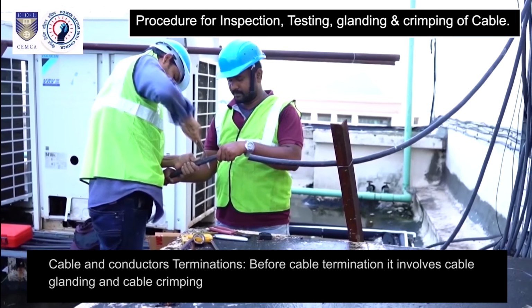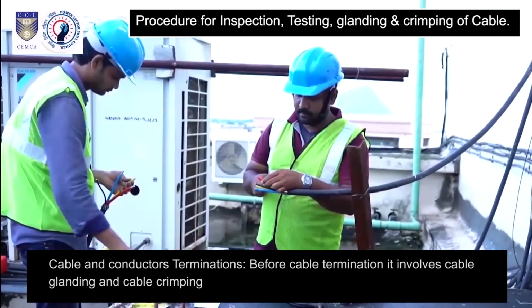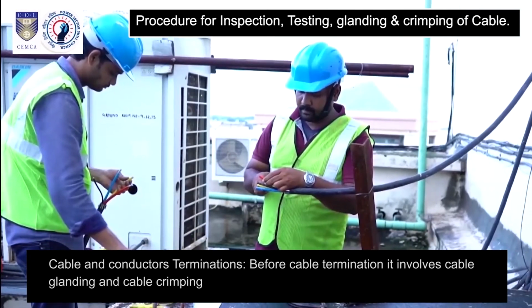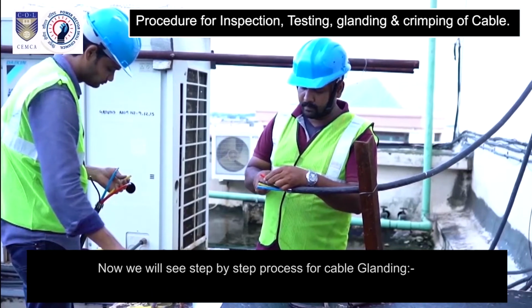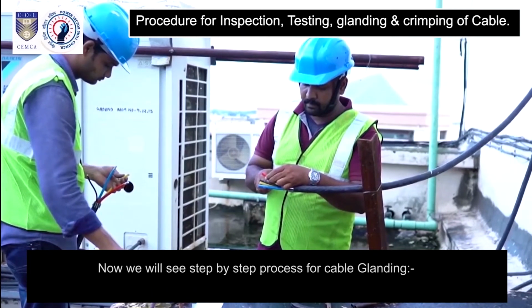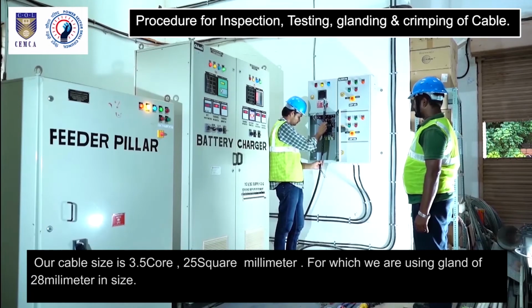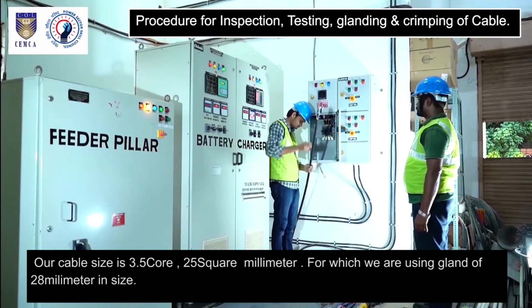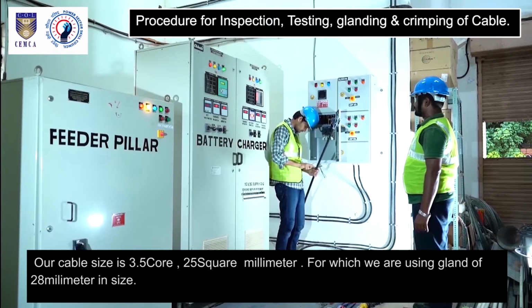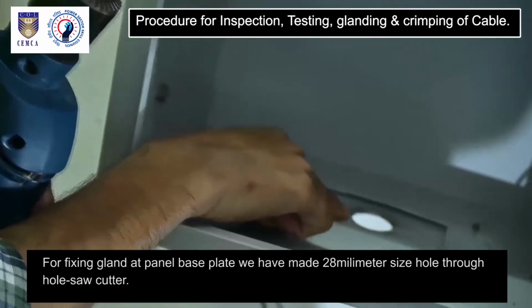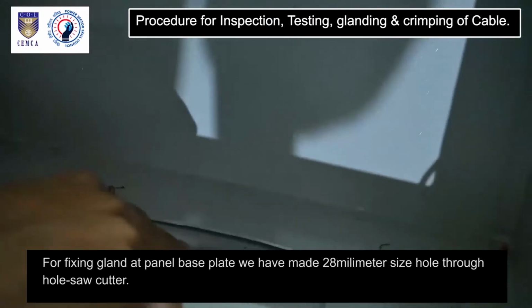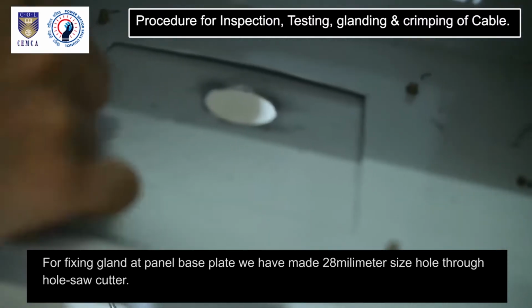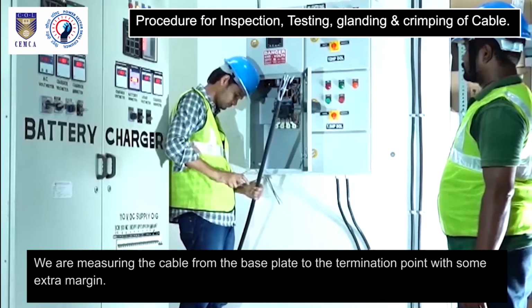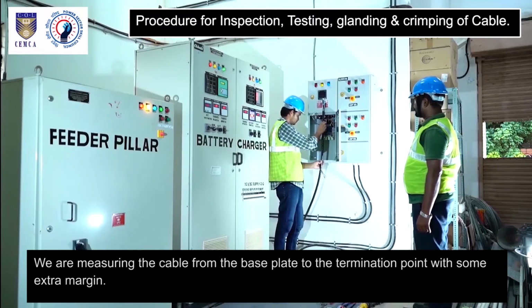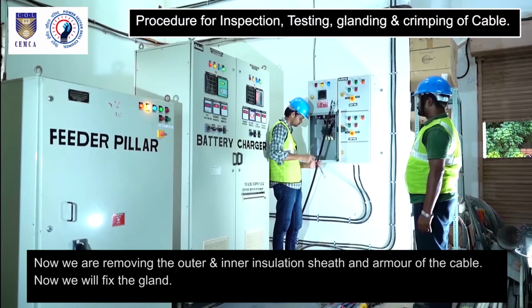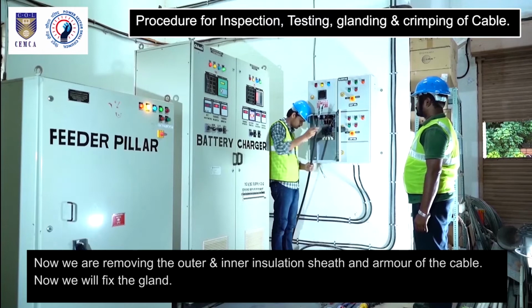Cable and conductors terminations. Before cable termination, it involves cable glanding and cable crimping. Now we will see step-by-step process for cable glanding. Our cable size is 3.5 core, 25 square millimeter, for which we are using gland of 28 millimeter in size. For fixing gland at panel base plate, we have made 28 millimeter size hole through hole saw cutter. We are measuring the cable from the base plate to the termination point with some extra margin. Now we are removing the outer and inner insulation sheath and armor of the cable.